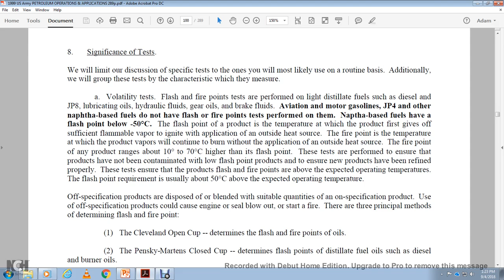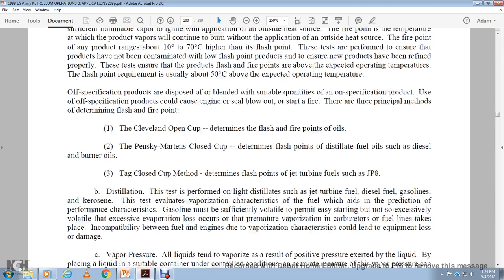Three principal methods of determining flash and fire point: the Cleveland open cup determines the flash and fire points; the Pensky-Martens closed cup determines the flash point of distillate fuel oil and diesel fuel oil; the Tag closed cup method determines the flash point of the jet turbine fuel JP8.